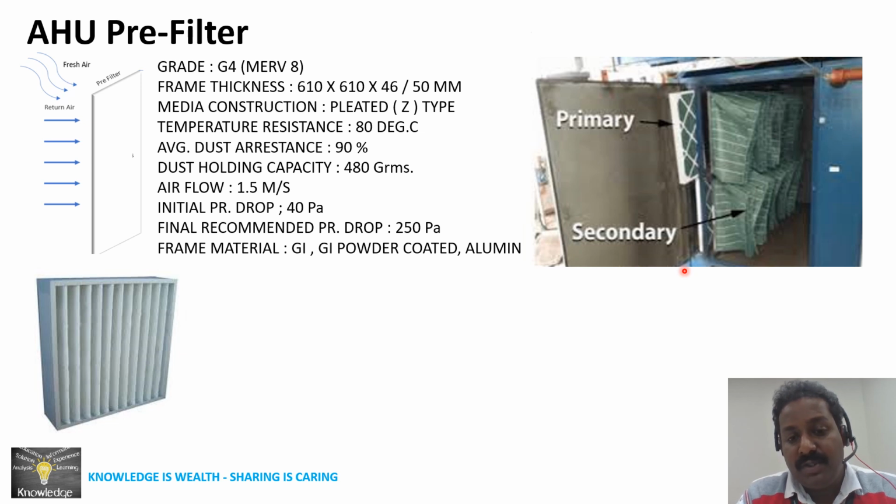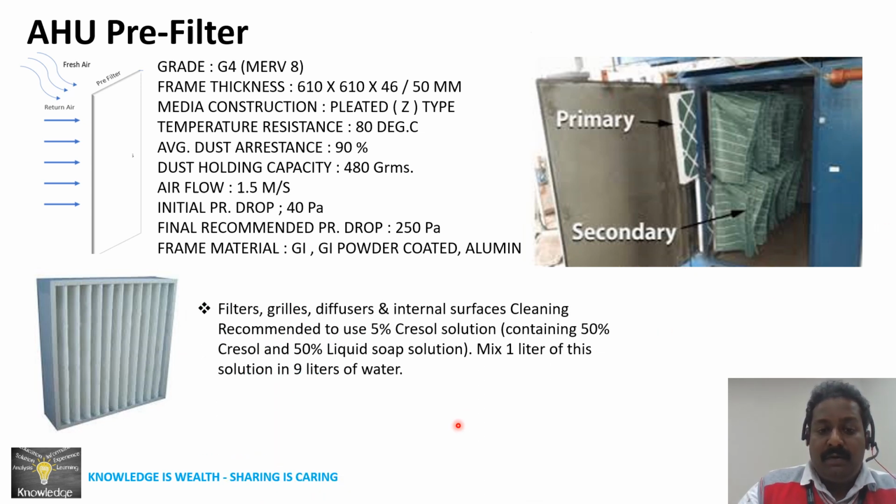Again, there is a norm that says we need to use a disinfection agent for the filter, not a chemical, okay. So we can use some disinfection agent, like 50% Cresol and 50% liquid soap, mixed, and you can make a Cresol solution. One liter of Cresol solution you can mix with 9 liters of water, and we can use it for the pre-filter cleaning activity.